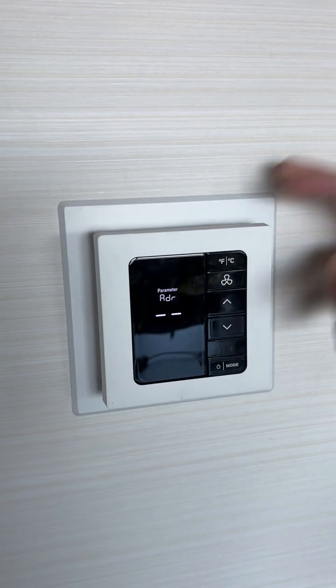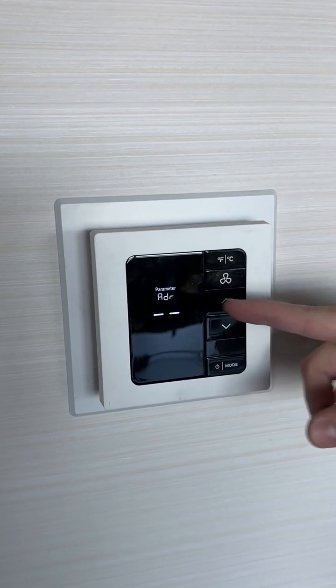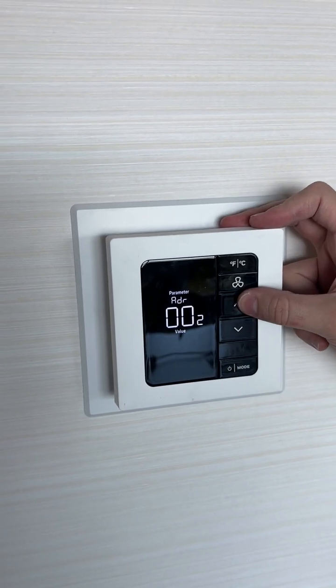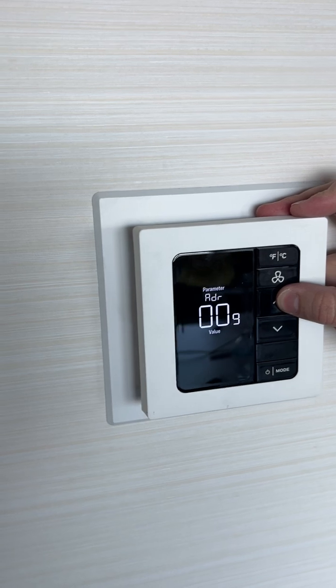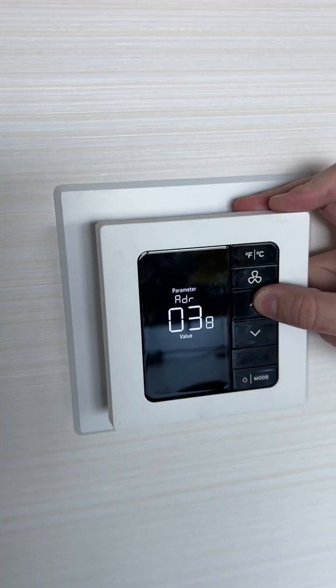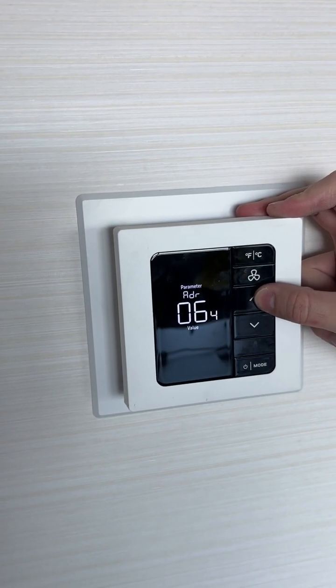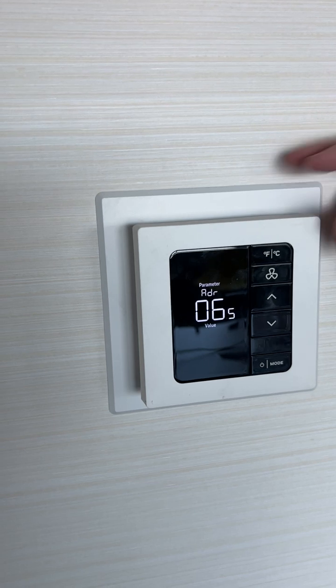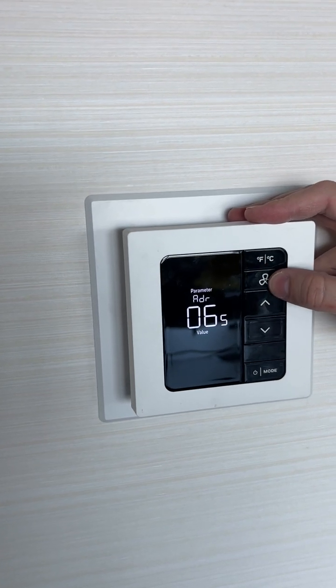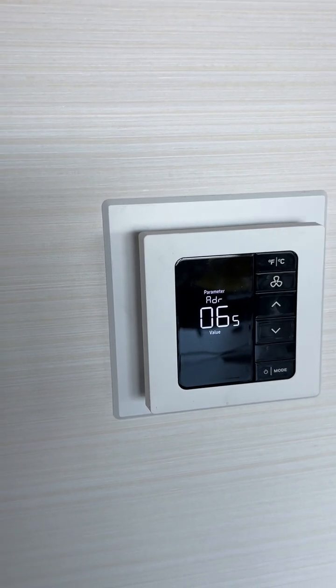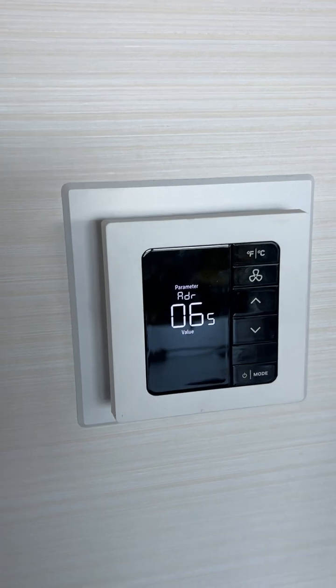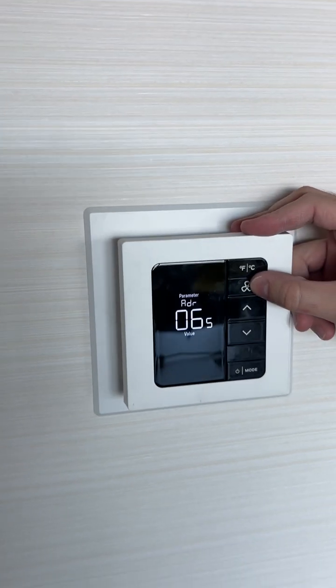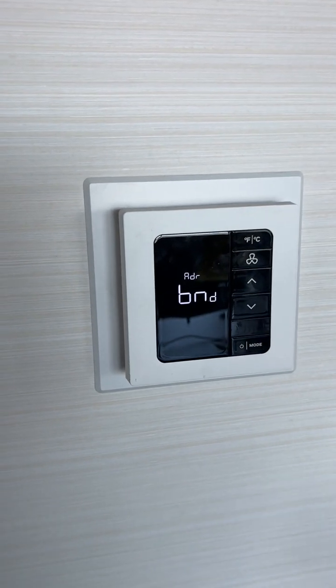ADR is where we'd go to bind the door lock. So we go ADR, mode to enter, and scroll up to 65. That's the address of the door lock—that's just how it was programmed. That's what the key card is referred to in our system as 65. So press fan, and this will start a 2-minute bind window.